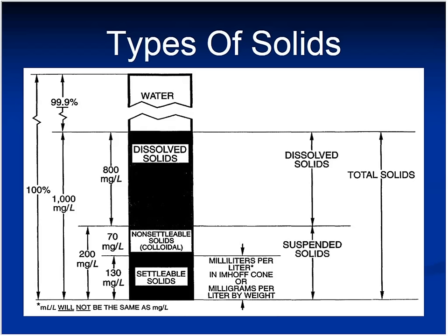These are solids that if we take a sample, set the jar on the bench, and let it sit there for about a half an hour, they're all going to drop to the bottom of the jar. The non-settleable solids, that stuff is just going to hang there and make that water look murky no matter how long it sits. It's colloidal material. It's very small, same density as water. It's got no reason to go up, down, sideways.